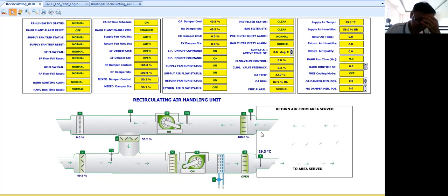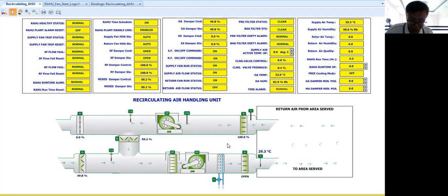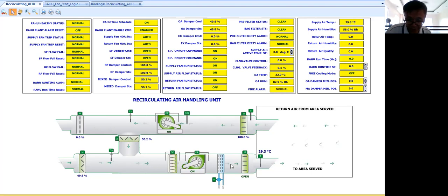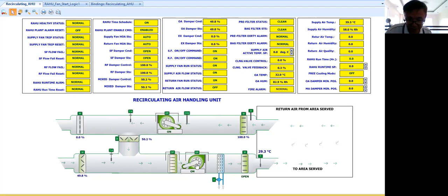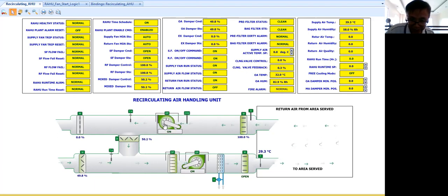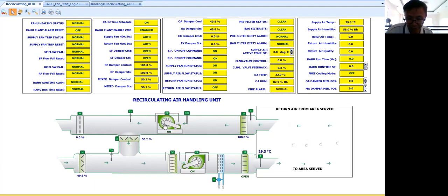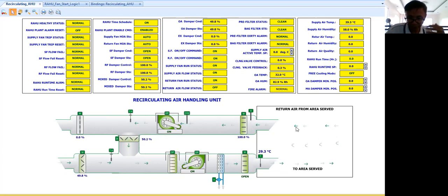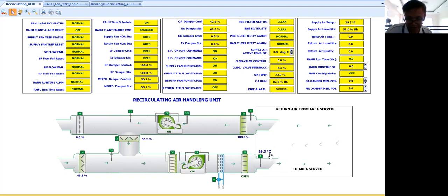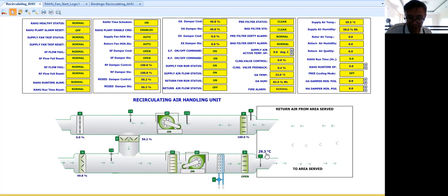As you can see, after these dampers assume some opening and this one opens a hundred percent, then that's the time to start the supply fan. Then after some time delay, I'm starting the return fan.